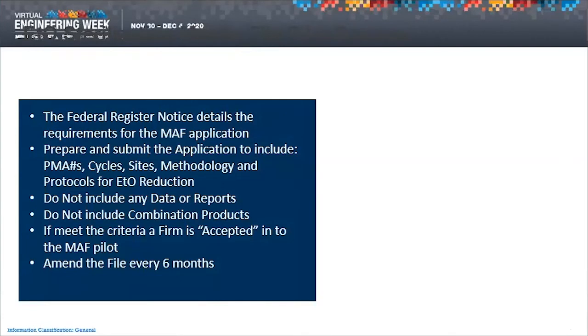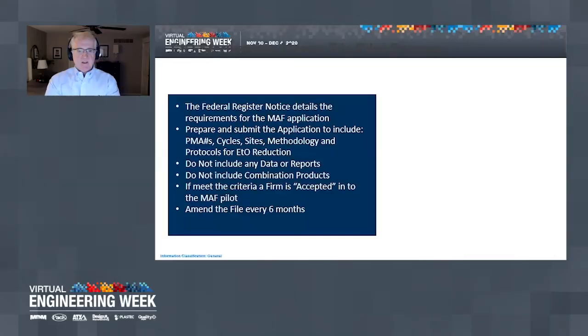Okay, so we're wrapping up here. The FR notice mentioned in the Federal Register is quite prescriptive and requires both the qualifications for the pilot and the information to be included in the application so it's accepted into the program. The scope of the master file includes all your PMA products you're selling, all the EO sterilization cycles you're running, if there's multiple, that are being targeted for reduction, the sterilization sites, including those worldwide or your global sterilization network, and the reduction methodology and protocols related to the validation of the reduced EO cycle.